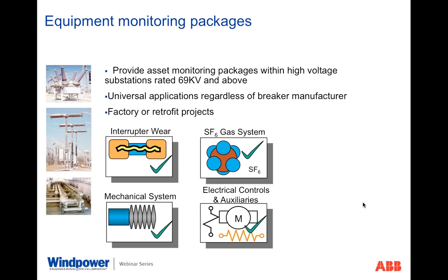In addition, for retrofit applications, ABB can provide installations on any breaker type. Retrofit projects have been targeted specifically for critical applications such as extra high voltage, cap bank, nuclear, hydro dam, and even remote wind farms. Our devices are installed in the breaker cabinet, as mentioned earlier, and use specific sensors to pull the necessary information into a microprocessor designed to provide advanced mathematical algorithms. For example, the interrupter wear algorithm uses the phase currents to provide gradual accumulation of interrupter wear, which will eliminate any intrusive inspections. This method provides a life expectancy of the interrupter based on the number of operations, either due to fault or basic switching situations.